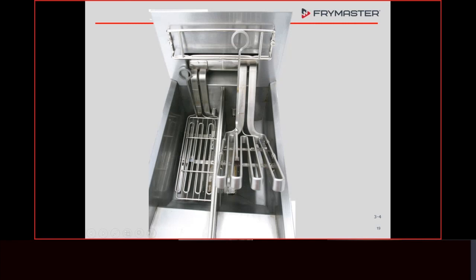Another thing, let your customers know, if they're doing a boil out or if they put new oil in this fryer, when it's heating up, make sure that they don't see little streams of bubbles coming up. That means that we got a hole in that element. They call those smokers because when it gets to the top, you get a little puff of smoke because it burns the oil up along the way.